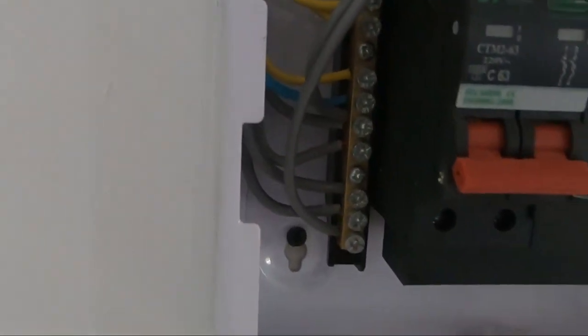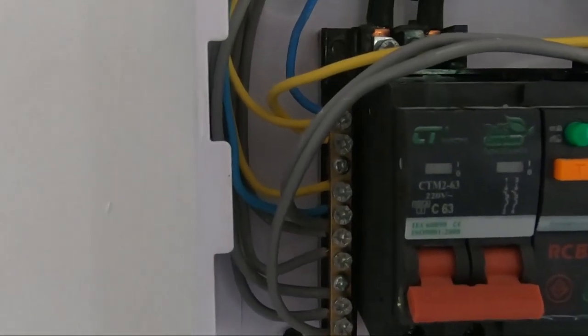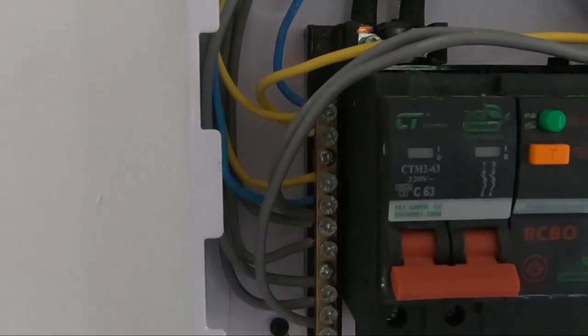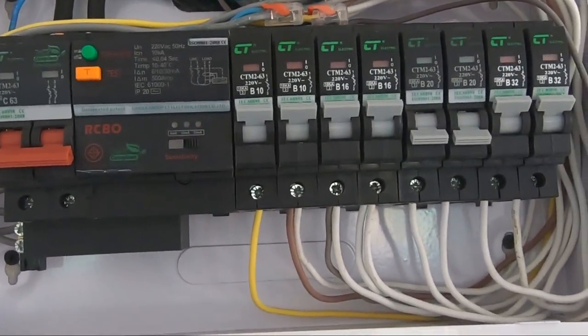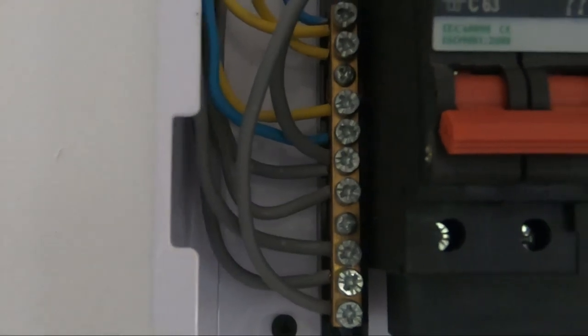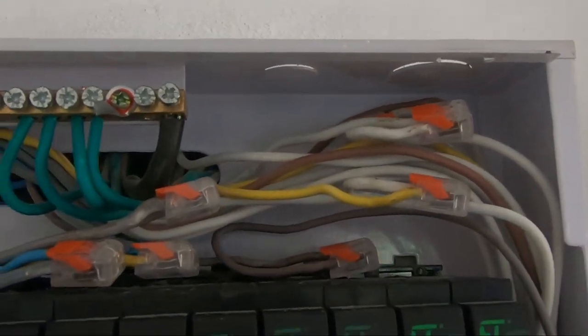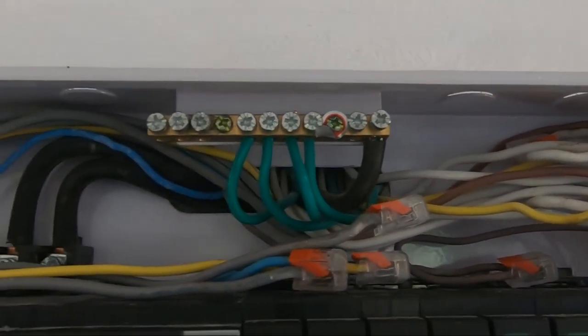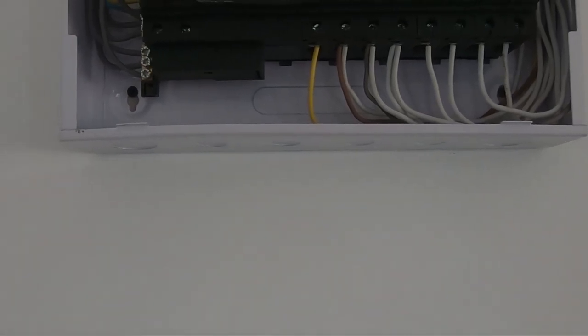I've tidied up this edge here a little bit. Basically, there's not as much exposed wire now. This might be half a millimetre on a couple of them. So I'm getting there. Yes, my freshly cleaned floor looking a bit worse for wear. Okay, I've done my bit. No wire showing now. The seven joints are done. So now the moment of truth is to turn the power back on and do some checks. Make sure I don't get any tripping.